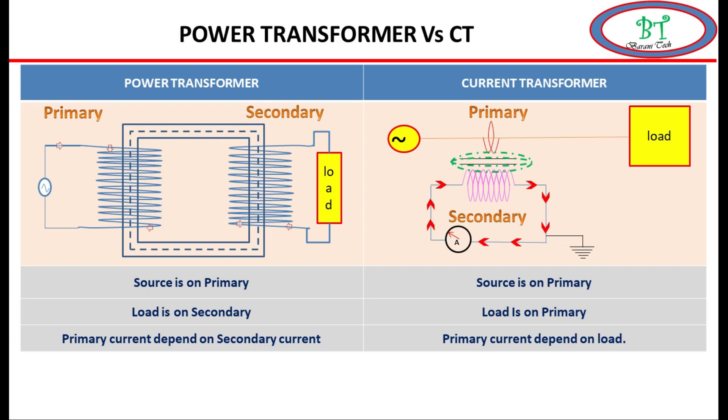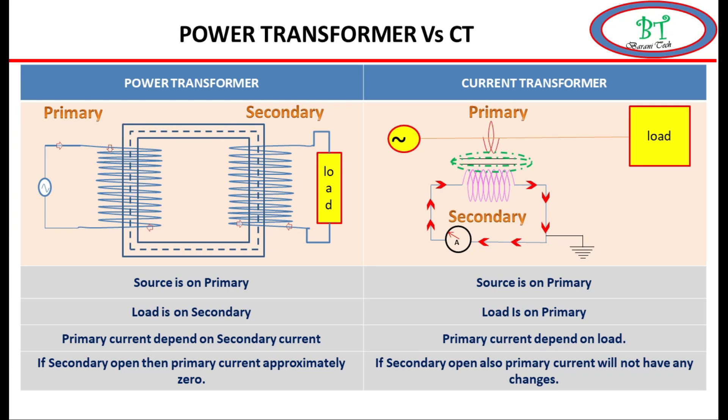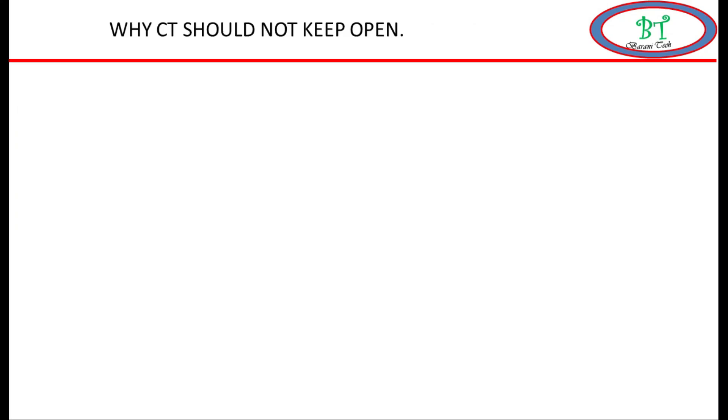For power transformer, if the secondary side gets open, the primary current approximately becomes zero. But for CT, even though the secondary side gets open, the primary current will not change. These are the major differences in working between power transformer and current transformer.